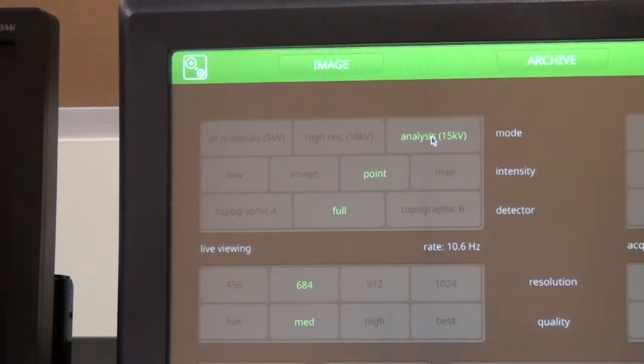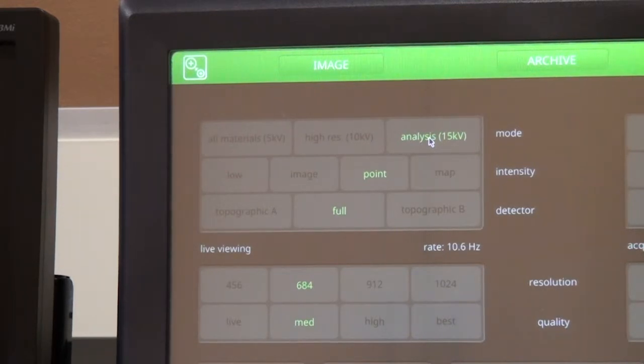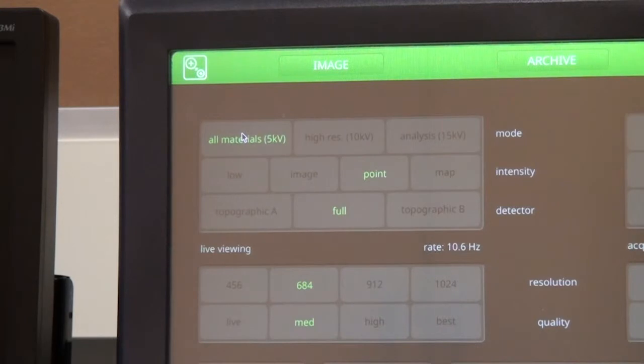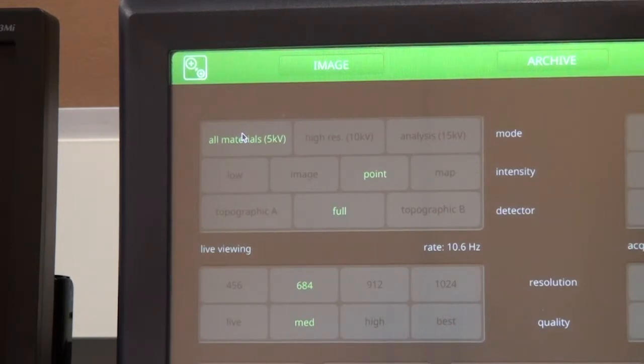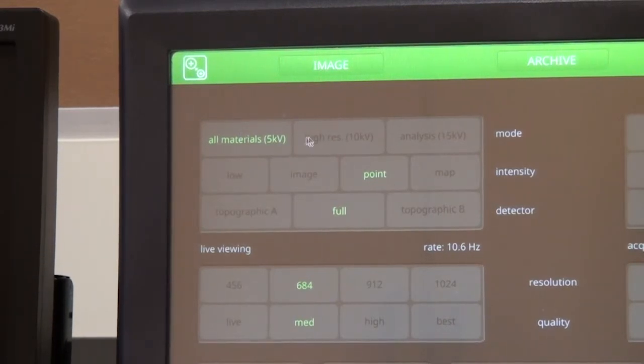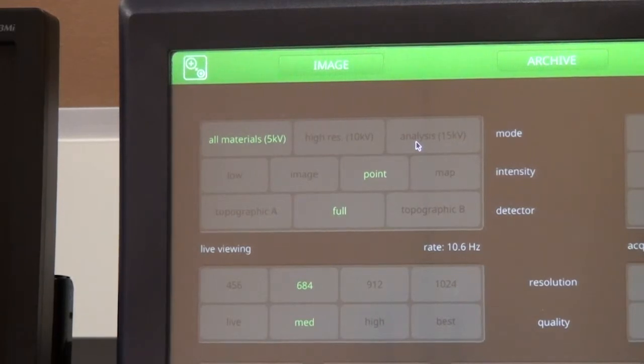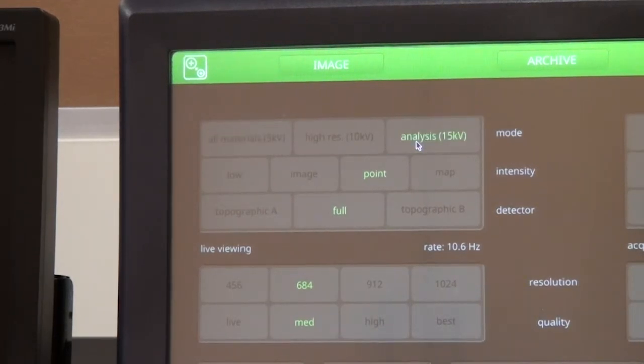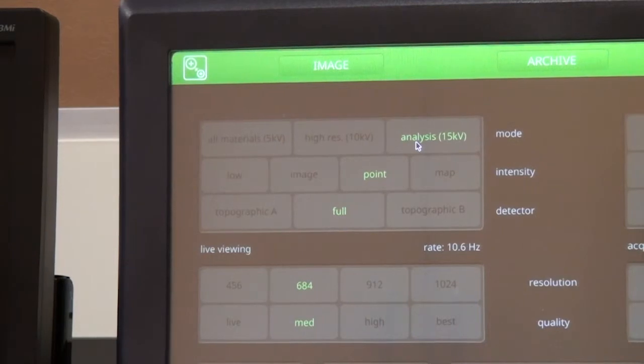The voltage controls the interaction volume of the sample, and also the electrons of the atoms in the sample that can be excited by the beam. At lower voltages, the area excited is smaller in depth, and we can see the finer details of the sample surface. But higher voltage is required for heavier elements in the sample, because the electrons in inner shells of the atoms will require more energy to become excited.